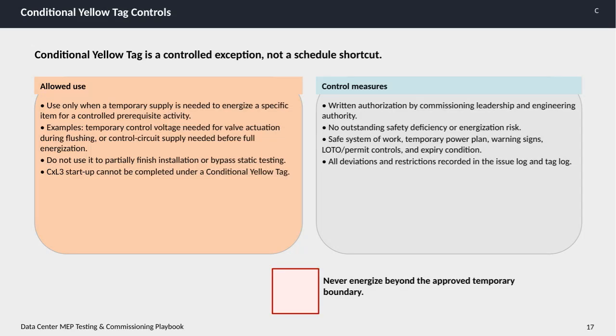On this slide, we're focusing on conditional yellow tag controls, which are essentially controlled exceptions rather than shortcuts to the project schedule. These tags allow for a temporary power supply, but only under very specific conditions. First, the allowed use. Conditional yellow tags are meant strictly for situations where a temporary power source is necessary to energize a particular item for a control prerequisite activity. For example, using temporary control voltage to actuate a valve during flushing, or supplying power to a control circuit before fully energizing the system. It's important to note that this tag should never be used to partially finish installation work or to bypass any static testing.